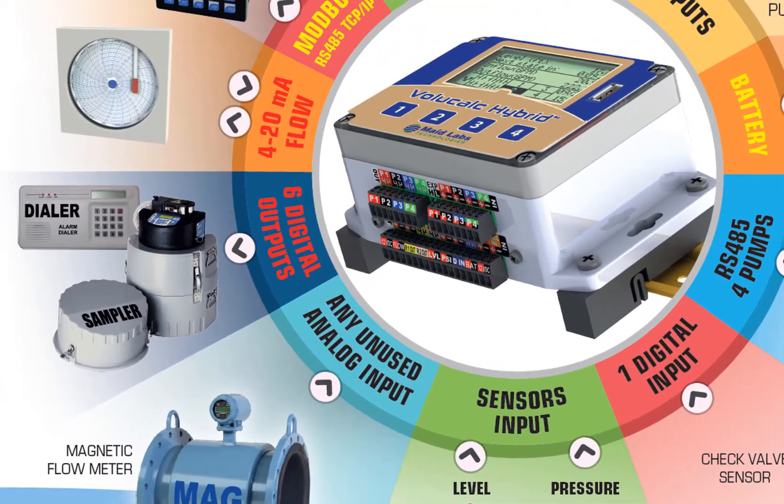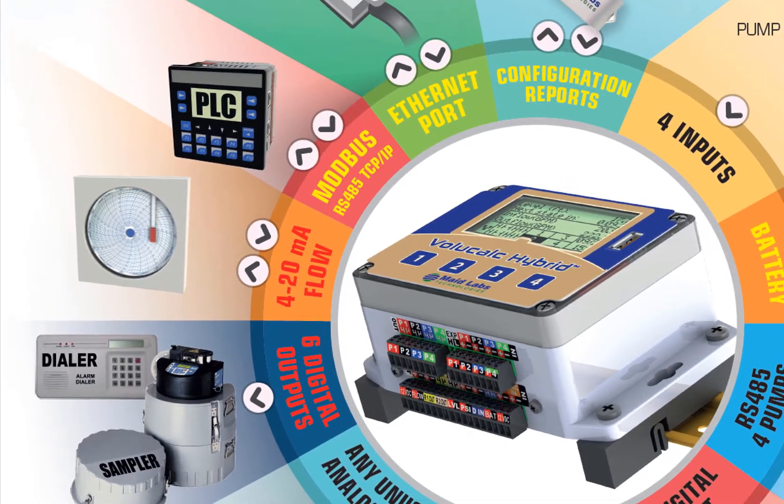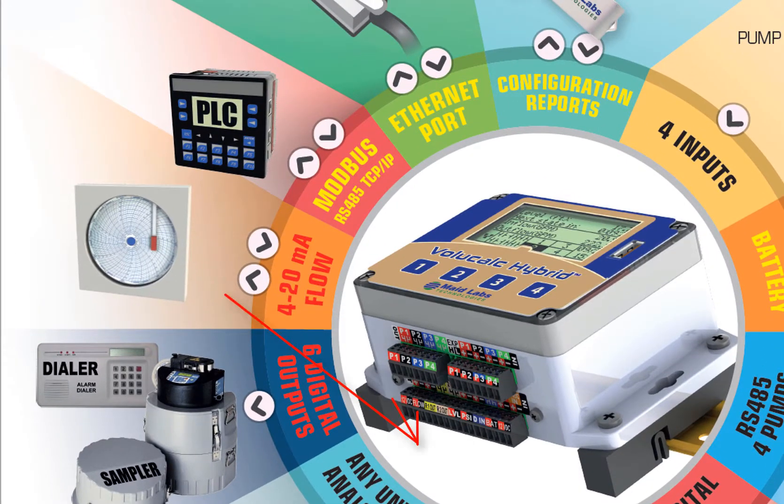We have six digital outputs on the Volucalc Hybrid. They can be used for a dialer, for flow proportional sampling, or made to close based on specific types of alarms. We also have a 4 to 20 milliamp output, which is proportional to the flow calculated in real time when the Volucalc Hybrid is connected to an analog level sensor. If it's not connected to an analog level sensor, it will wait until the end of a cycle to calculate the average flow during that cycle.